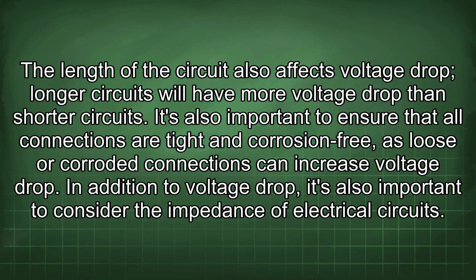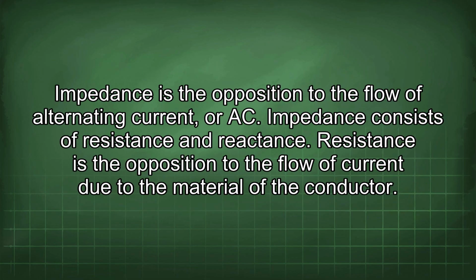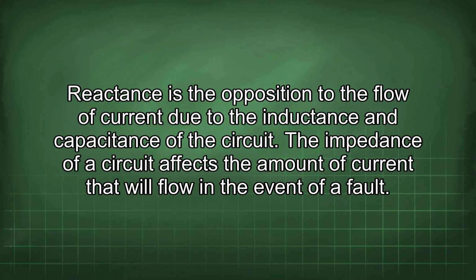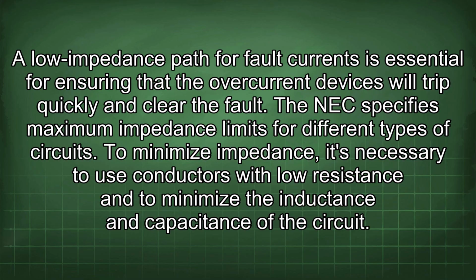drop. In addition to voltage drop, it's also important to consider the impedance of electrical circuits. Impedance is the opposition to the flow of alternating current, or AC. Impedance consists of resistance and reactance. Resistance is the opposition to the flow of current due to the material of the conductor. Reactance is the opposition to the flow of current due to the inductance and capacitance of the circuit. The impedance of a circuit affects the amount of current that will flow in the event of a fault. A low impedance path for fault currents is essential for ensuring that the overcurrent devices will trip quickly and clear the fault. The NEC specifies maximum impedance limits for different types of circuits.